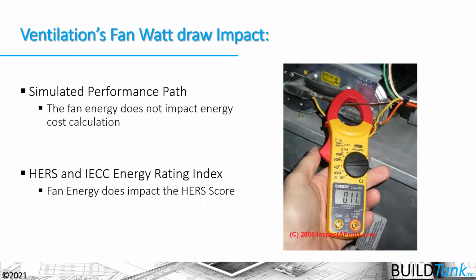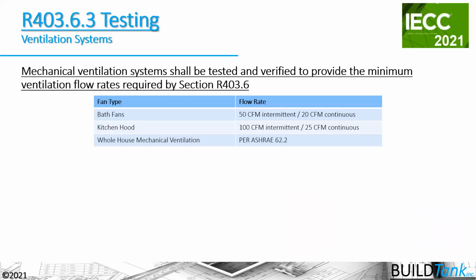Again, a reminder that we want the most watt-draw efficient, so the lowest watt-draw fans in these systems, regardless of whether it's supply, exhaust, or balanced ventilation, and that watt draw will have an energy penalty on the house, whether it's used or not for code or the HERS index. In the 2021 IECC, there's a new requirement that mechanical ventilation systems shall be tested and verified to provide the minimum ventilation flow rates required by the ventilation section of the code here. So we're actually going to be testing the fan to see if it's able to blow 50 CFM in that bathroom, 100 CFM in the kitchen, and then the whole house mechanical ventilation rate.